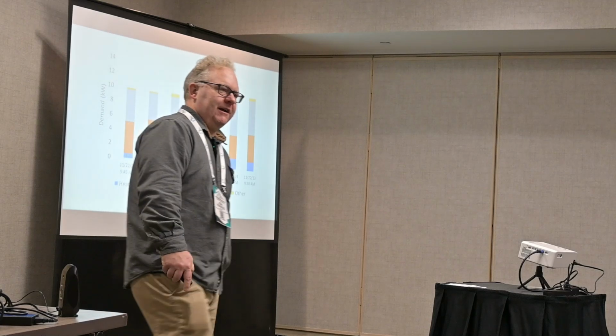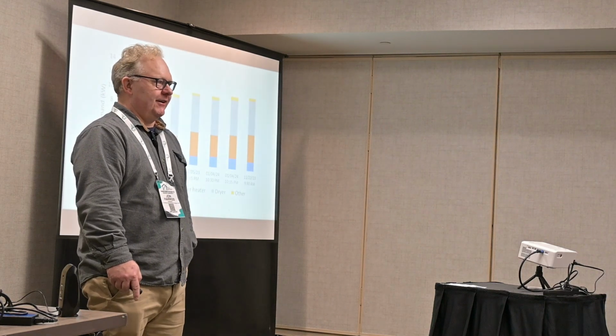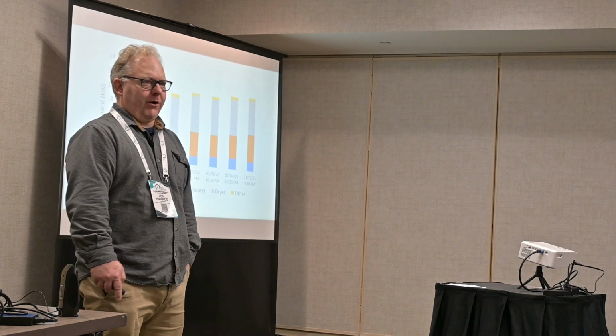I wouldn't do this in a customer's home until I'd done it in my home, but I did really tight sizing calculations, and I was able to get by with a 1.5 ton heat pump for the whole house. My house has similar parameters to yours. Is your system running at max all the time at the 1.5 ton, or are you finding that it's running on a lower output? It's modulating the whole time. When we get below zero outside, which happens a few hours each year, it does slip a little bit. I'm willing to accept that, honestly, but that's not a choice I would make for a customer.